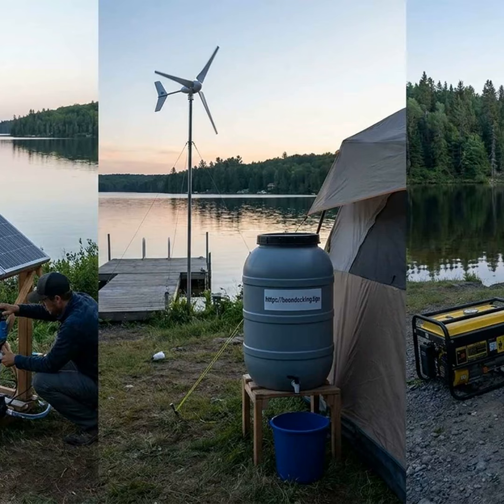Backup generator. A propane or diesel generator, near 3 to 5 kW, provides emergency power when renewable sources dip. Multi-day storm or winter. Store enough fuel on site for at least a week of intermittent use. A manual charging device, 12-volt battery charger, can also trickle charge the battery from the generator's 12-volt output if needed.